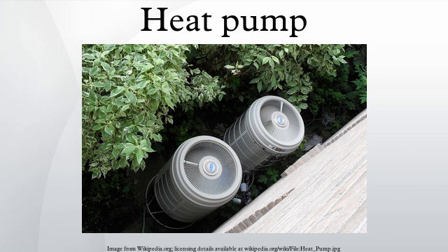The design of the evaporator and condenser heat exchangers is also very important to the overall efficiency of the heat pump. The heat exchange surface areas and the corresponding temperature differential directly affect the operating pressures and hence the work the compressor has to do in order to provide the same heating or cooling effect. Generally, the larger the heat exchanger, the lower the temperature differential and the more efficient the system becomes. Heat exchangers are expensive, requiring drilling for some heat pump types or large spaces to be efficient, and the heat pump industry generally competes on price rather than efficiency.